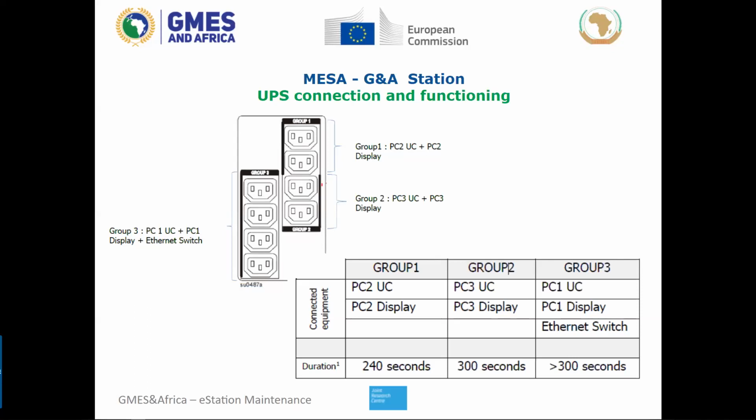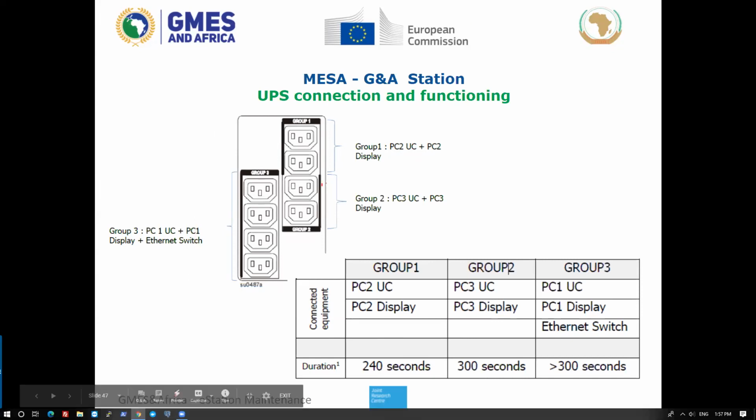That was also the problem that maybe you spotted when we presented the dashboard. So this is another element to keep in mind: the UPS communicates with the rest of the Mesa station. The 3 computers have to be in the same LAN with the correct configuration, and the UPS has to be connected to the computers when you do the installation of the Mesa station on the computers themselves. Yeah, thanks, that was my remark.